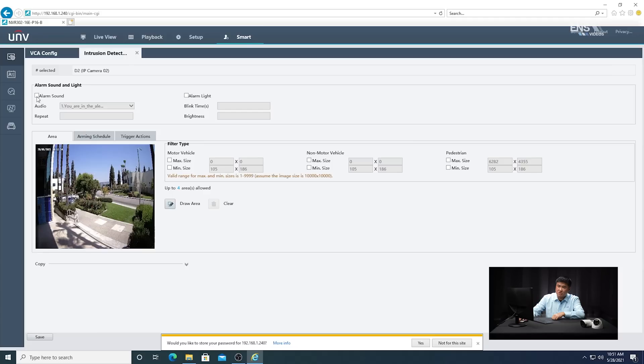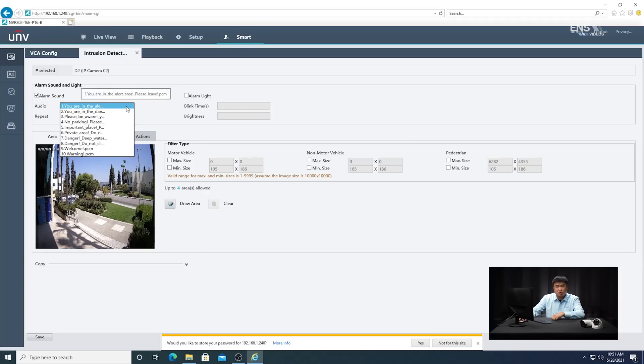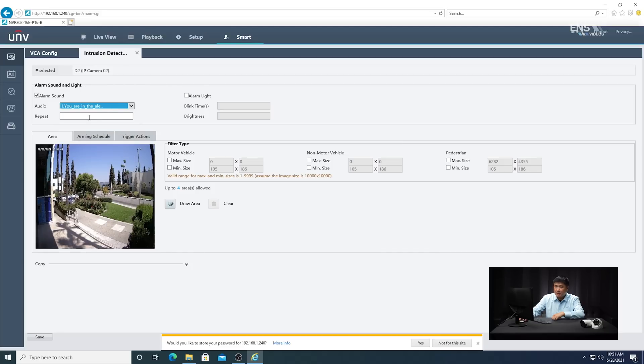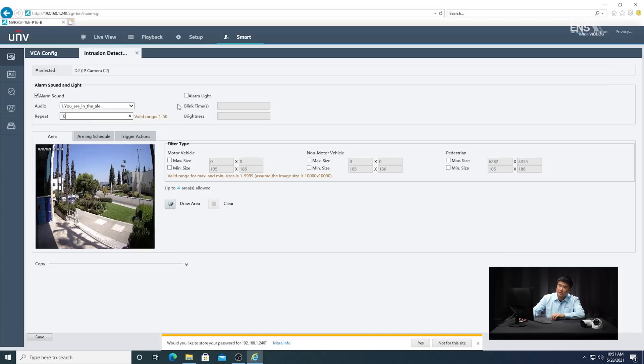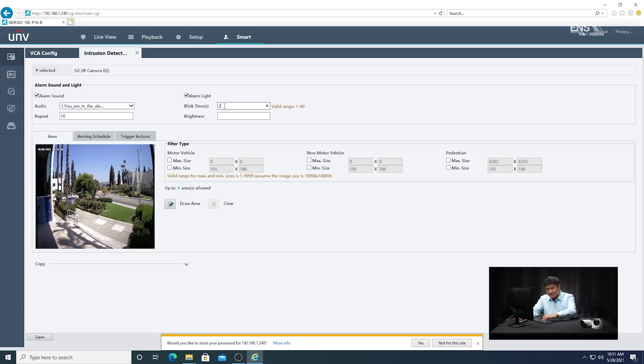I'm going to check alarm sound, and then you have a drop-down menu of different messages it can output when triggered. In this example, I'm going to select 'you are in the alert area, please leave.' Right below that, I'm going to select the repeat — that's how many times the message will repeat, so I'll put 10 as an example. Under the checkbox for alarm light, I'm going to enable that. It's an optional strobe light that can coincide with the alarm message. Select the blinking time and the brightness level, which is between 1 to 1000, based on the lighting environment.